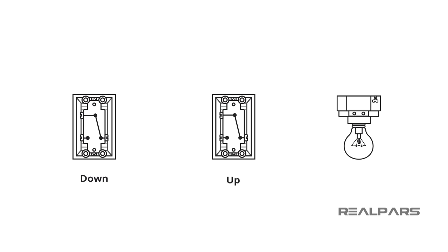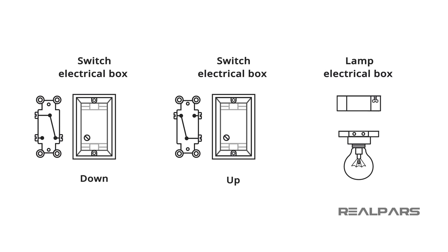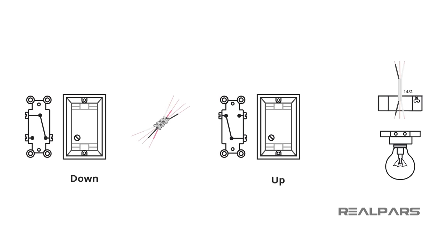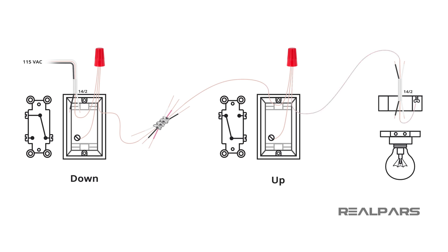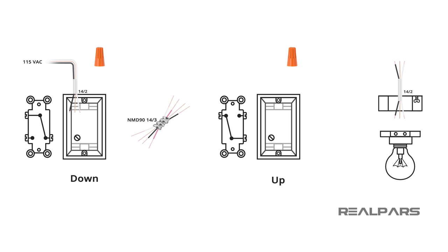Each device will be contained in an electrical box in the wall and ceiling. The electrical power enters through the down switch electrical box. For all electrical circuits, the bare earth ground wires are connected and bonded to each electrical box. We have introduced a new cable called NMD-90-14-3, which has a third red wire. The electrical power black wire connects to the down switch common terminal. The power white wire does not connect to the switch at all, but is connected to the white wire of the 14-3 cable. The wire connection is completed inside the switch electrical box.